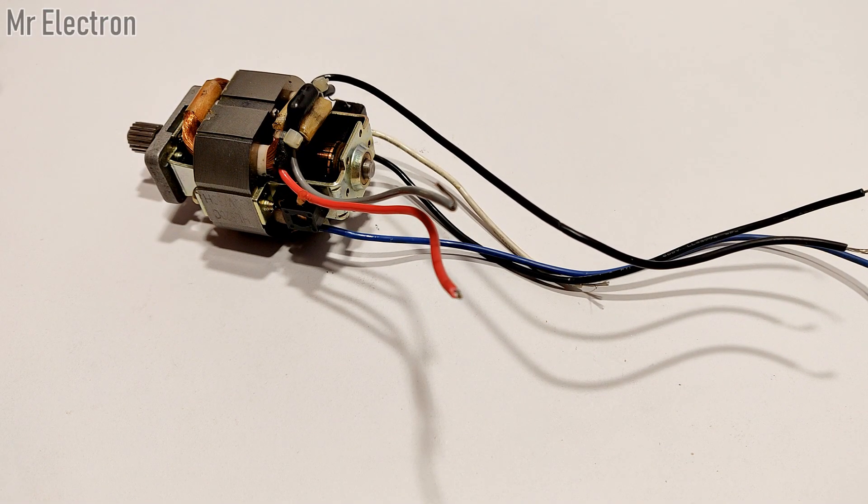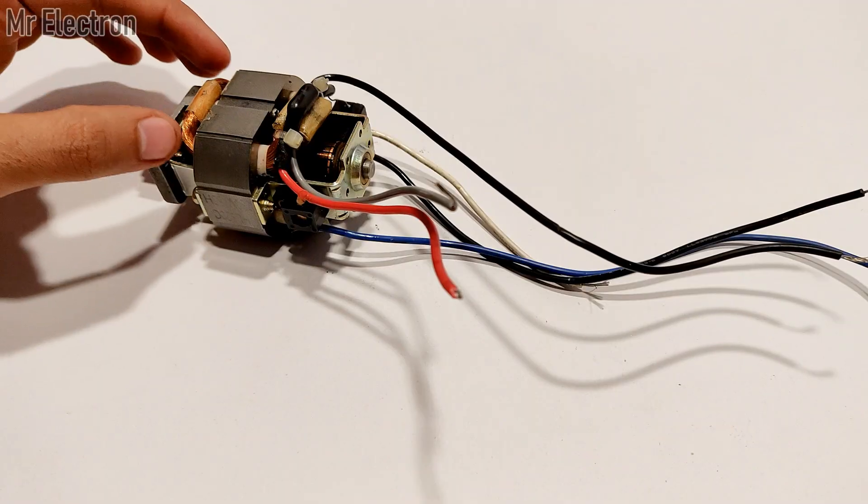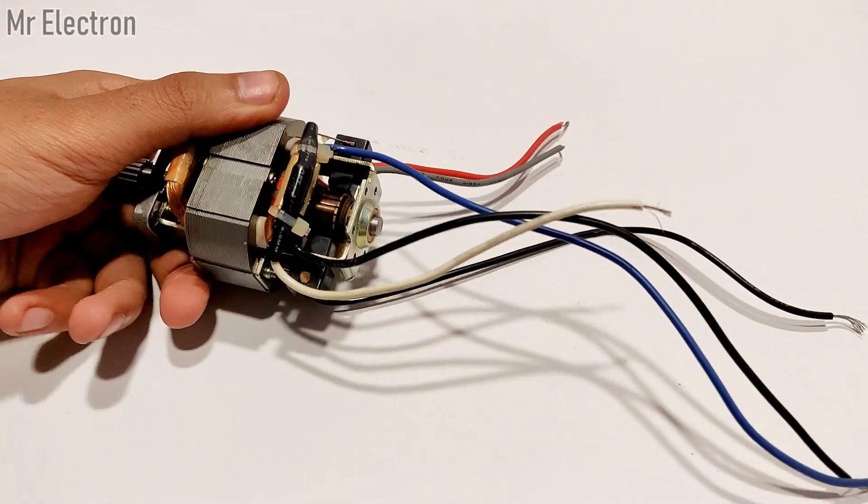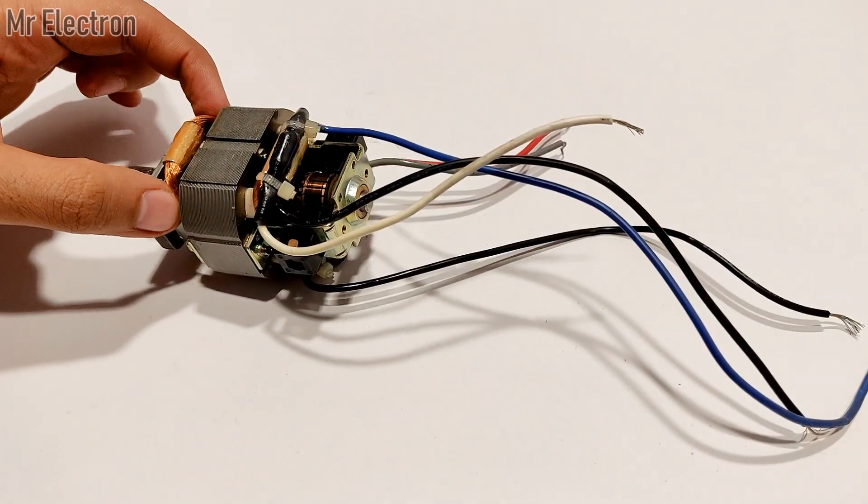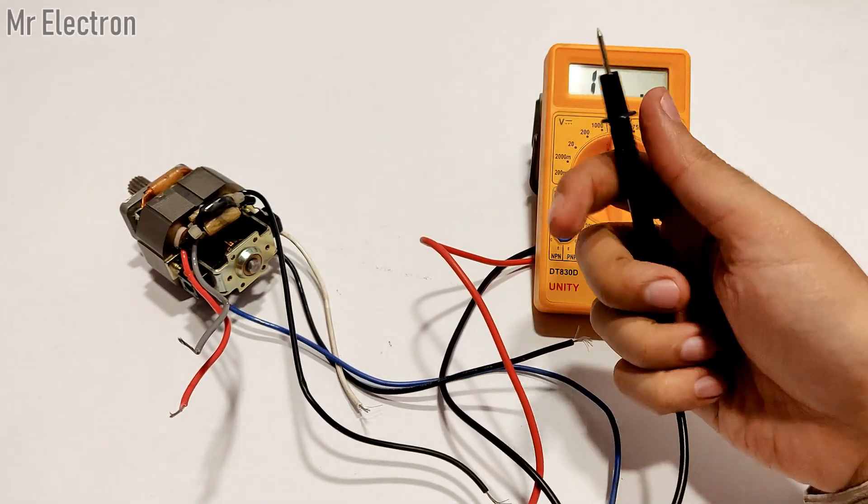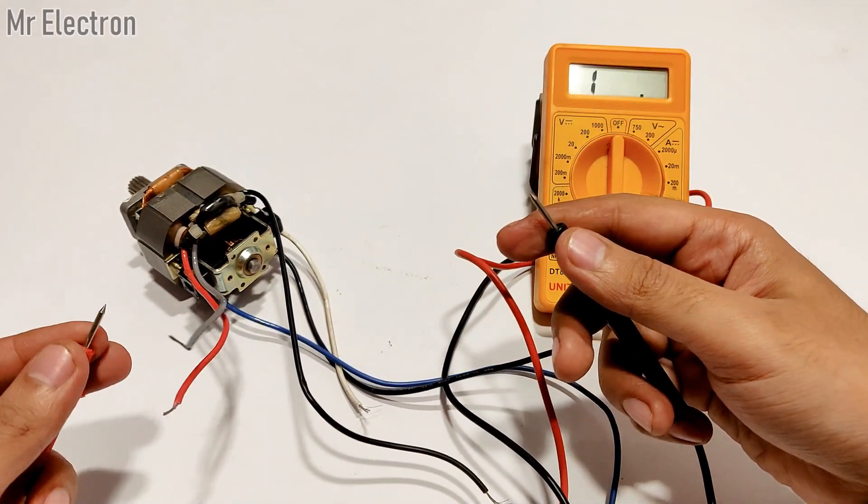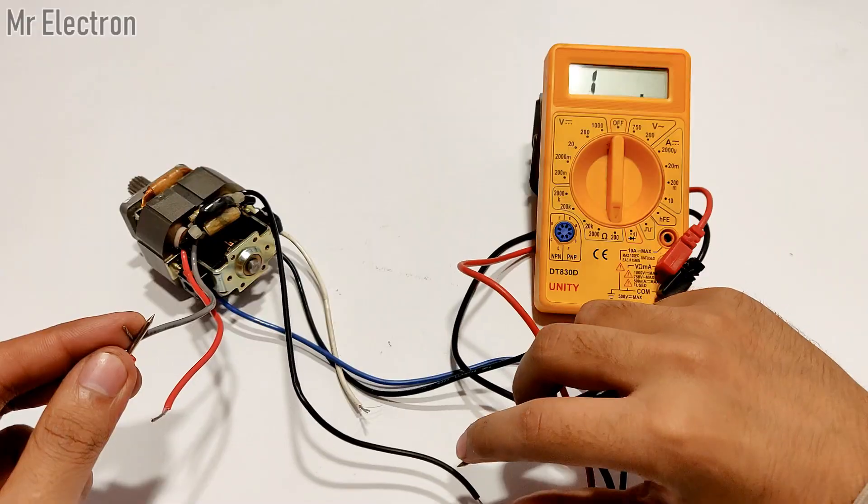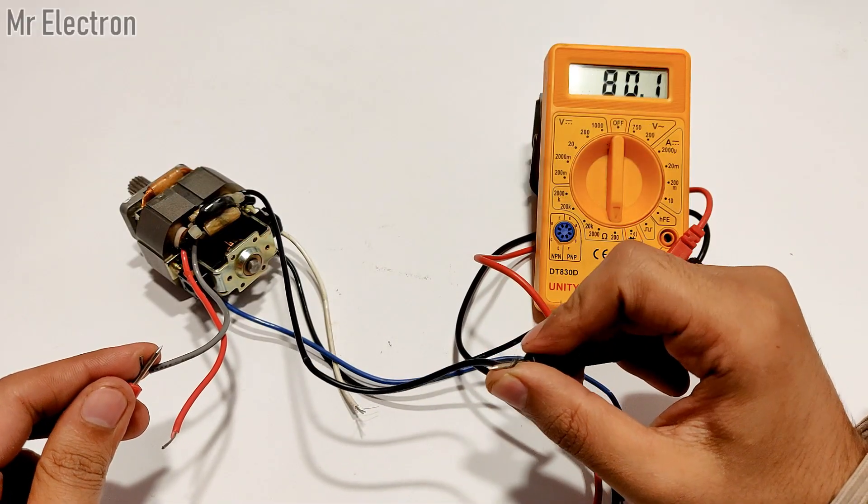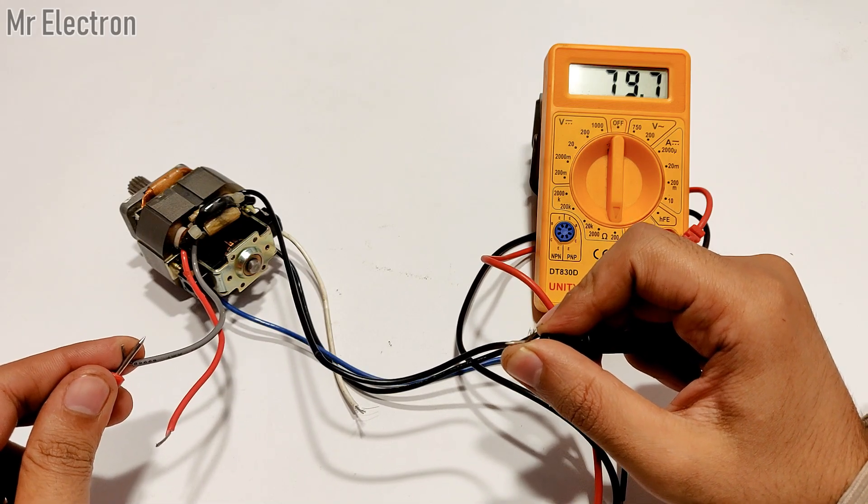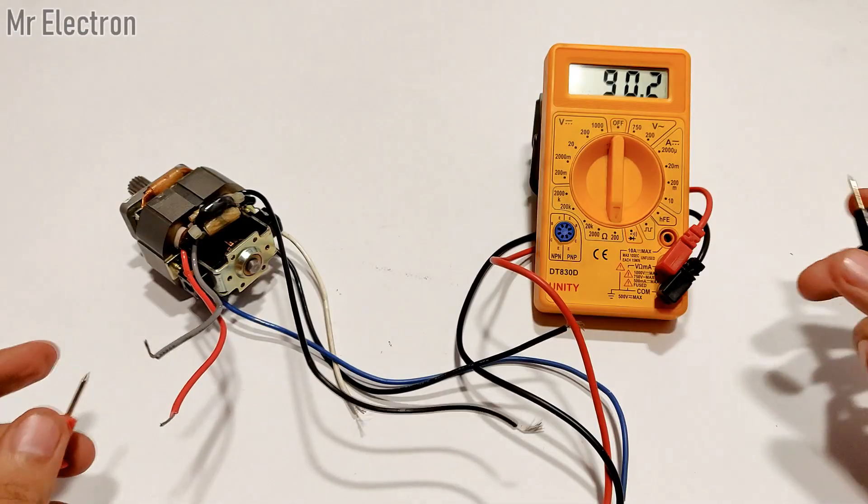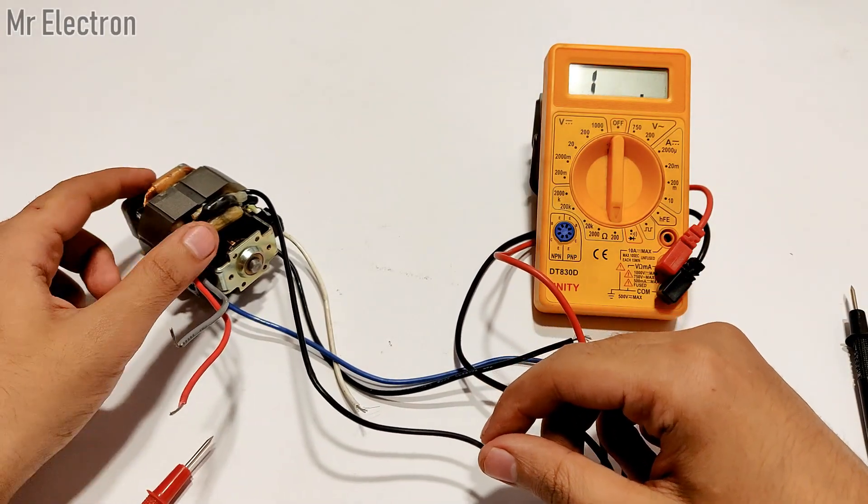First, I will check the two output wires from this field winding, then I will check the two output wires from this field winding. The gray wire and the black wire, as you can see, are showing a resistance of 79.6 ohms, almost 80 ohms. So these coil side output wires are gray and black.